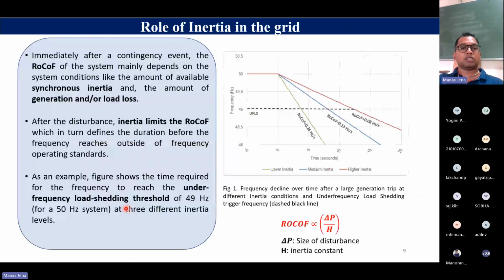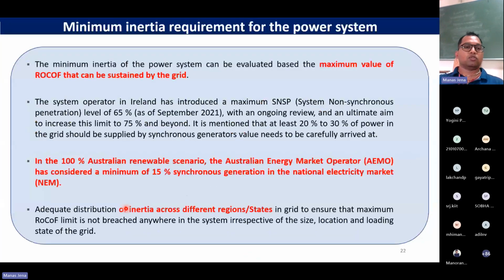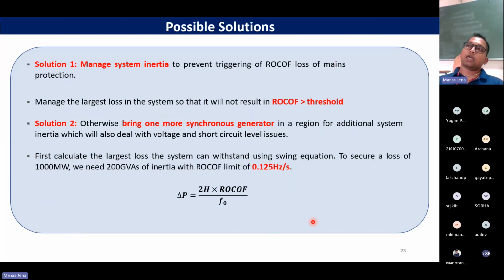And the operators too have also identified adequate distribution of inertia across different regions and states in the grid, to ensure that the maximum RoCoF limit is not breached anywhere in the system, irrespective of the size, location and loading. You can see now that the maximum penetration problem essentially boils down to how much is the maximum RoCoF you can survive or withstand. What are the solutions?